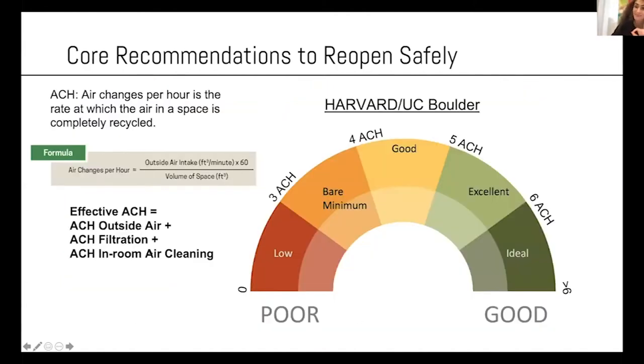The key here is that the air exchange rate doesn't only have to do with outside air. This is really important. Specifically, if you don't have outside air by design, it can be filtration from indoor air filters, and it can be portable air cleaning, or in-room air cleaning. If you put in filters, it's very easy to achieve a very high air exchange rate. I will show you an example later. We now call this metric effective air exchange rate. It's a sum of any device that can give you air cleaning, on one condition: you need to know the efficiency and the airflow. You can't just make up a number, you actually need to know it and apply it. So outside air, filtration, and in-room air cleaning.